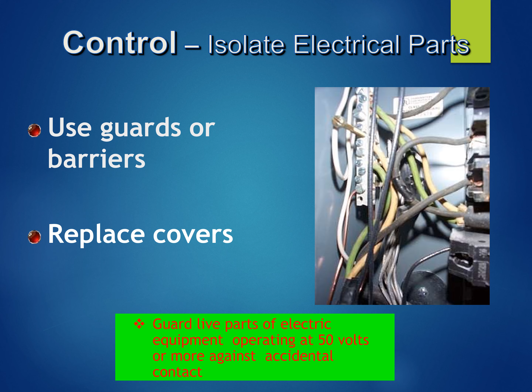Any conductor entering or leaving a junction box or panel board must be protected. All unused openings must be covered to prevent the ingress of insects. Otherwise, this will cause arc flash, which is dangerous to humans working with those boxes or panel boards.